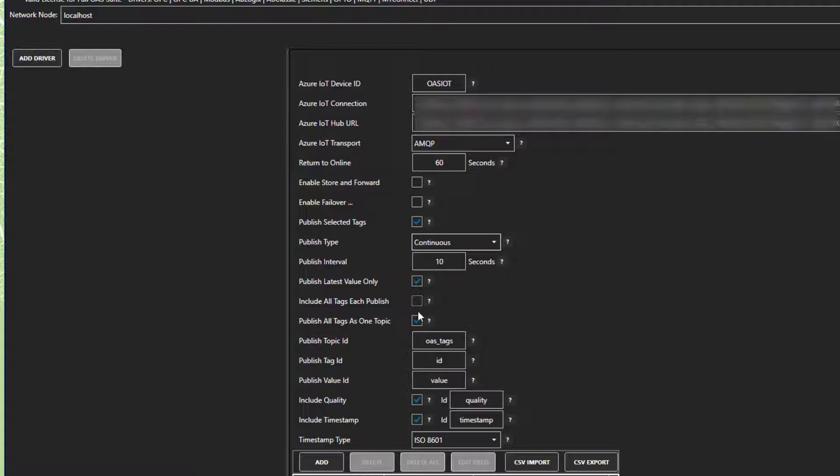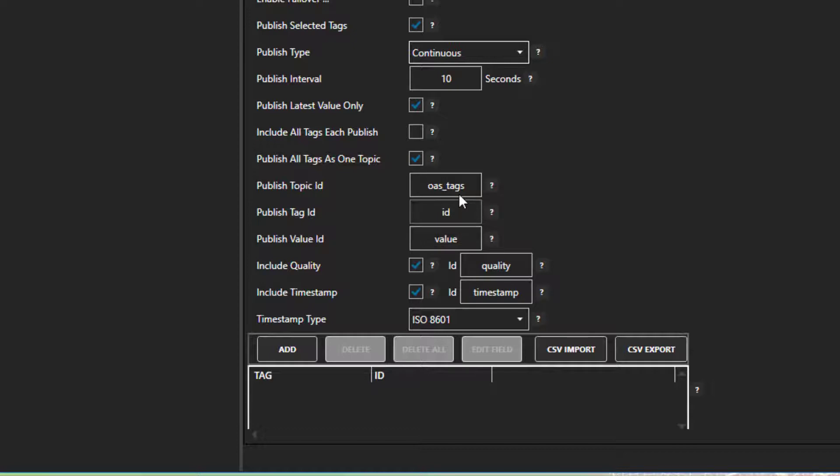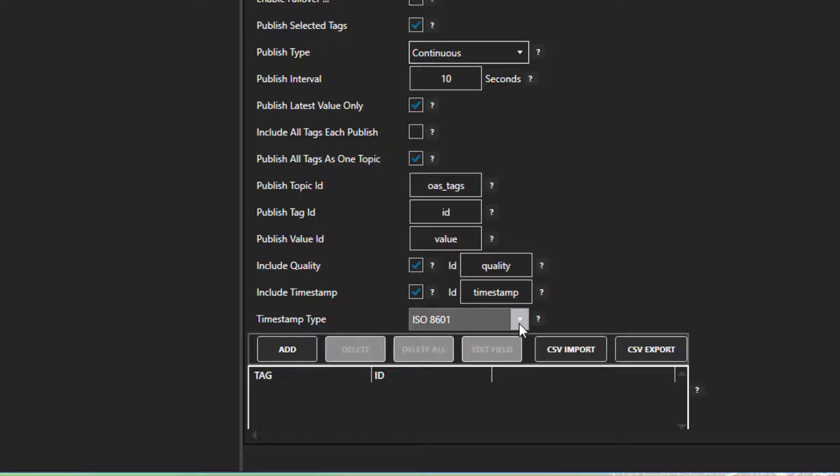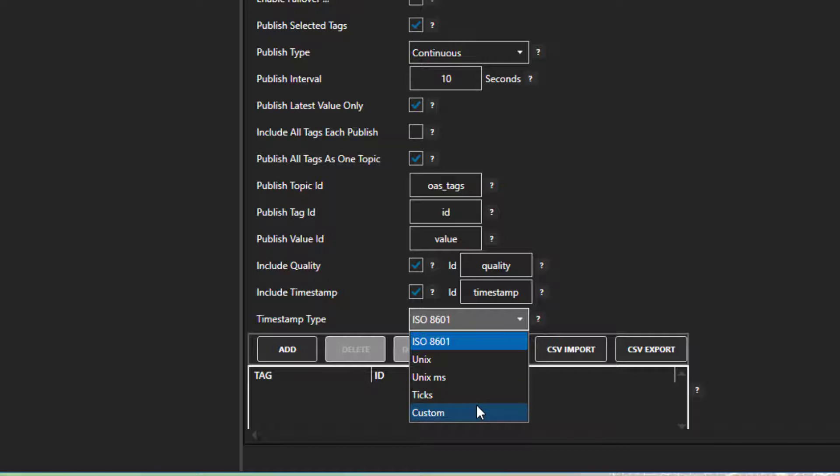The next box, Publish all tags in one topic. If this is checked, it will send all of the tags that we select in one topic. The JSON packet will include tag ID, value, quality, and timestamp. You have the option to change the key names for those here. You can also uncheck Include Quality and Include Timestamp if you don't want to include those. There is a timestamp drop-down to change the timestamp format. It defaults to ISO 8601. There is also Unix time in seconds or milliseconds, ticks, which are equivalent to 100 nanoseconds, and custom, where you can specify your own format.